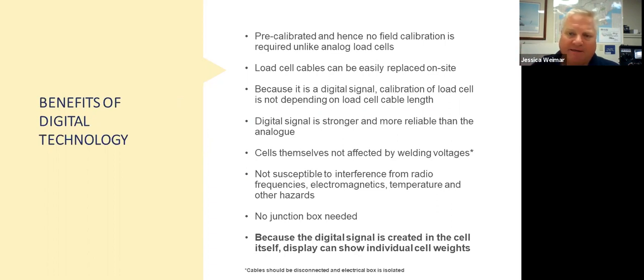In addition, there's another thing that's pretty cool about this system. Think about an analog strain gauge system. When you have a strain gauge, it's measuring a resistance change. And what does that mean? It means that the length of the wire that's attached to the cell has an impact on the resistance that the system sees. In other words, in a strain gauge, I'm going to be measuring the resistance change in the gauge itself. In order to do that, I've got to know what the resistance in the wire that it's connected to is, right? And if I change that wire, or I cut that wire, or I modify that wire, I've got to recalibrate the system because I've changed the resistance because I may have changed the length.